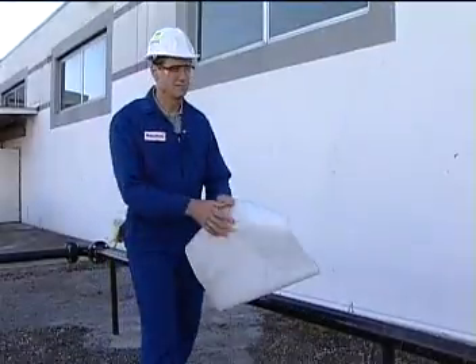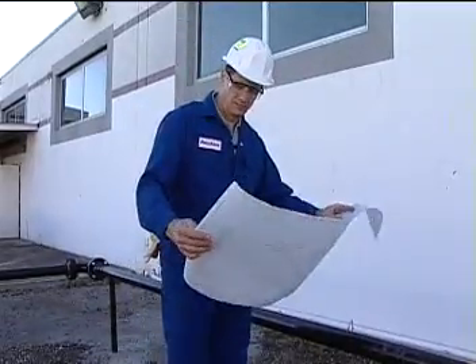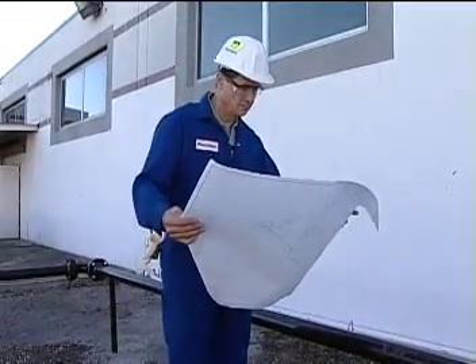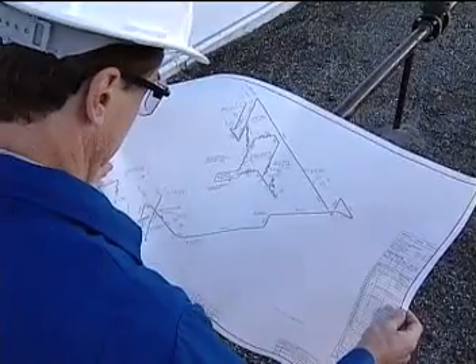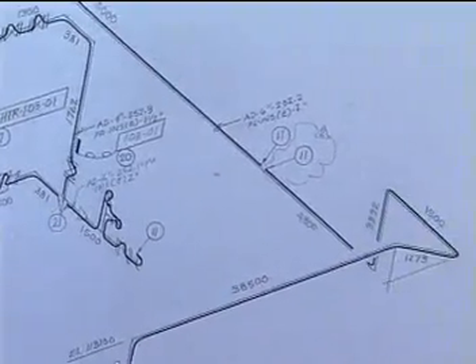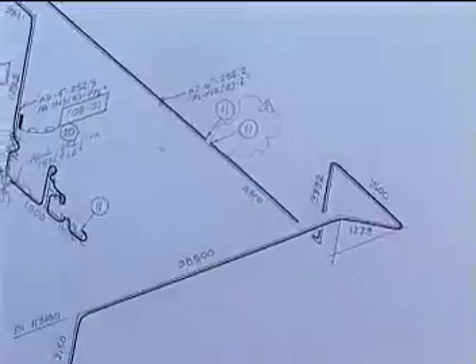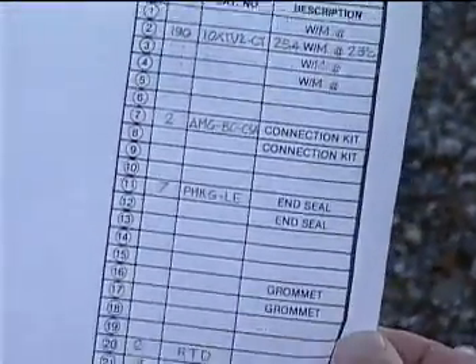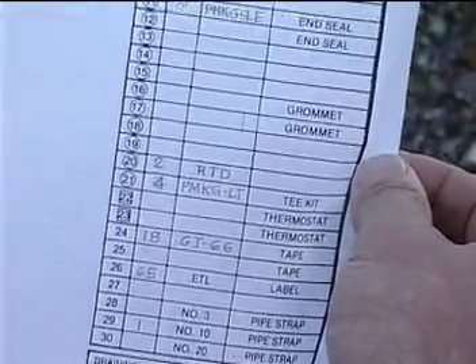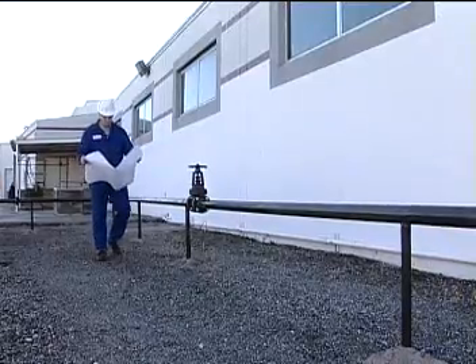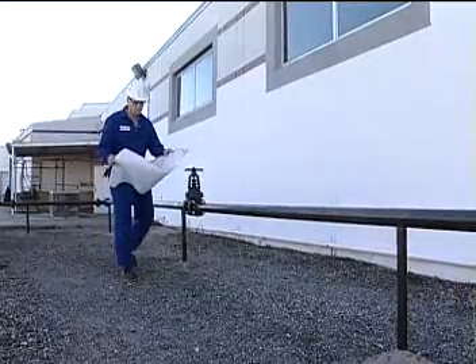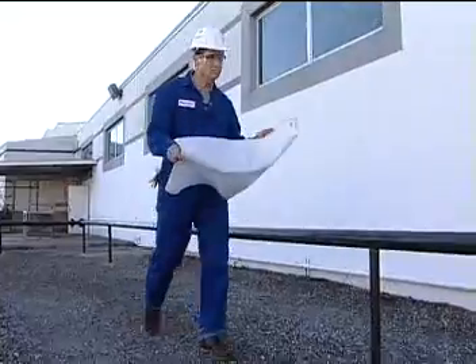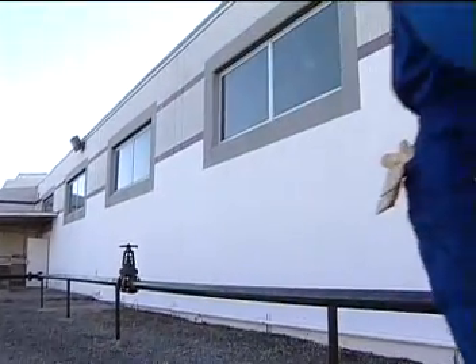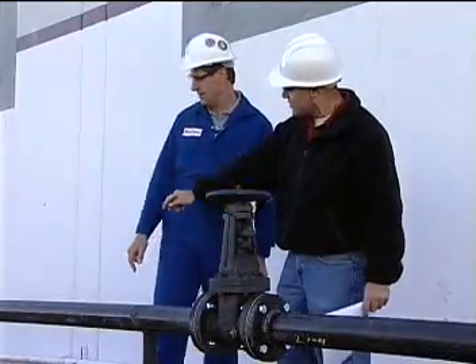Before you begin installing the heat tracing system, there are some initial steps that we recommend you take. First, take the time to look over the design drawing so you're familiar with the layout. The drawings will help you verify the actual pipe layout and give you a list of the specified components. If the design drawings are not available or if the design has changed, you can field verify them to create a bill of material. These drawings will help you determine where the heat tracing components should be positioned, as well as verify the quantity of supports, valves, pumps, or any additional accessories you'll need before pulling the cable.